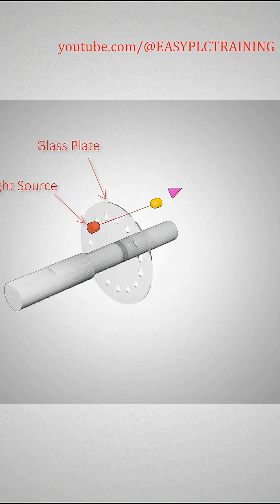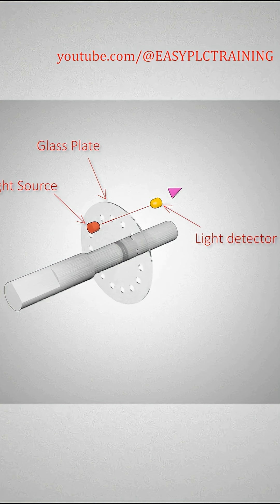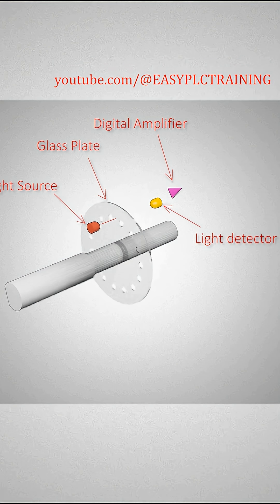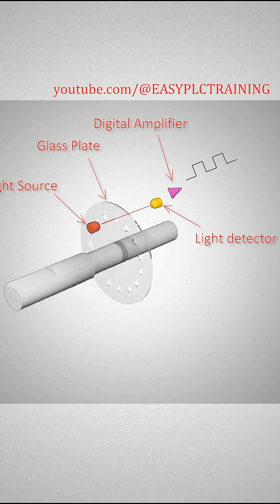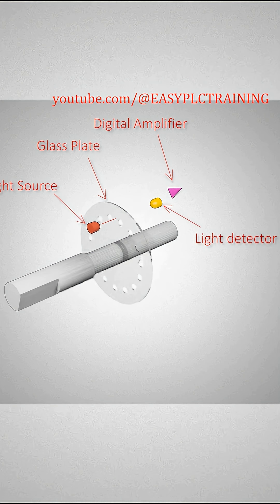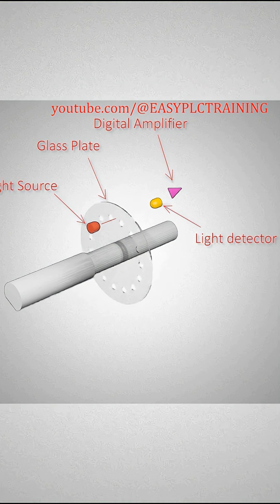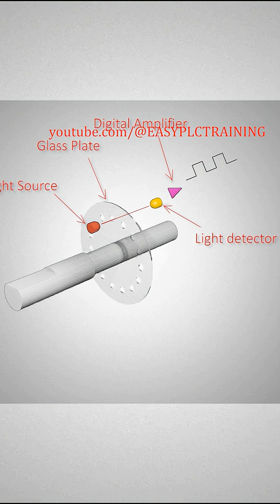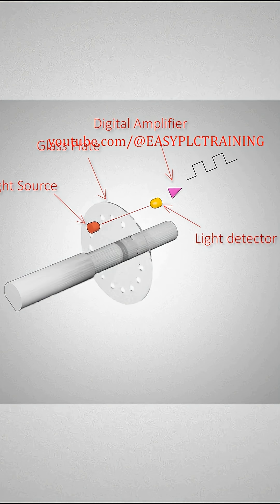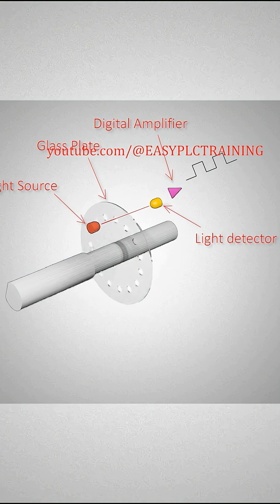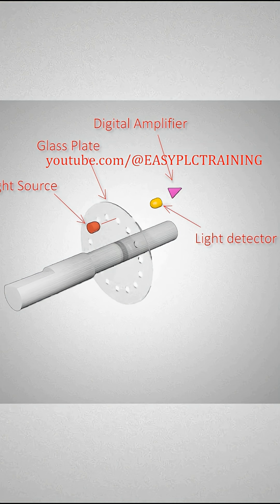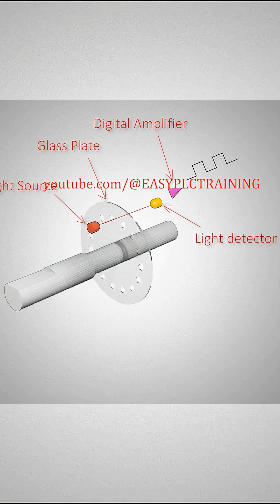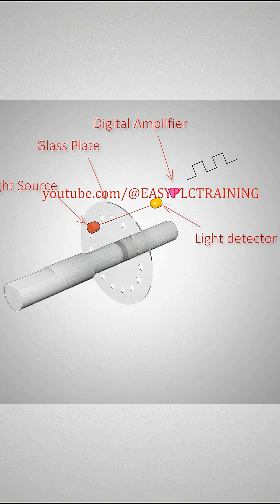Near the glass plate, you will find a light source on one side and a light detector circuit on the opposite side. This light source continuously emits a beam of light. As the encoder shaft rotates, the glass plate also rotates. As soon as the light beam and a hole in the glass plate become aligned, the light beam passes through the hole and the light detector picks up this signal. This signal is then amplified and converted into a digital pulse output. This is a simple example of how an encoder works and what's inside it.